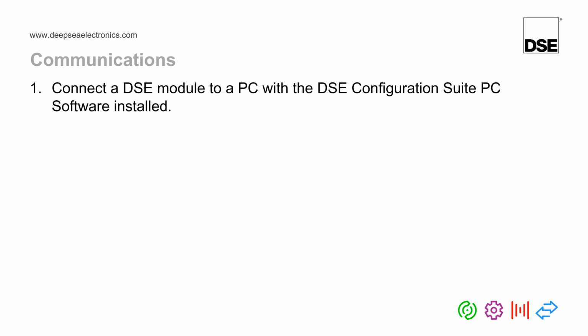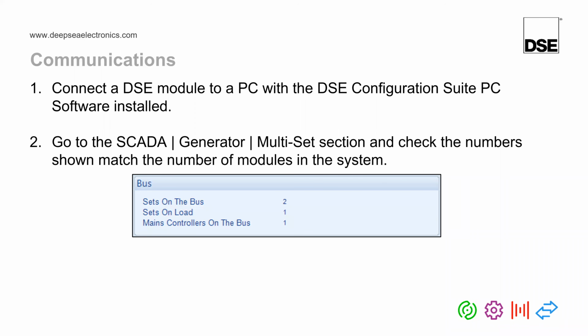What you first need to do is connect your DSE module to a PC with the DSE configuration suite software installed. Then you go to the SCADA section of the DSE configuration suite, and you go to SCADA, generator, and multi-set. Then you simply check that the numbers on screen match the numbers of controllers you have. Sets on the bus relates to how many 8610s you have connected on the MSC link, and mains controllers on the bus refers to how many 8660 or 8680 controllers you have connected on the bus.